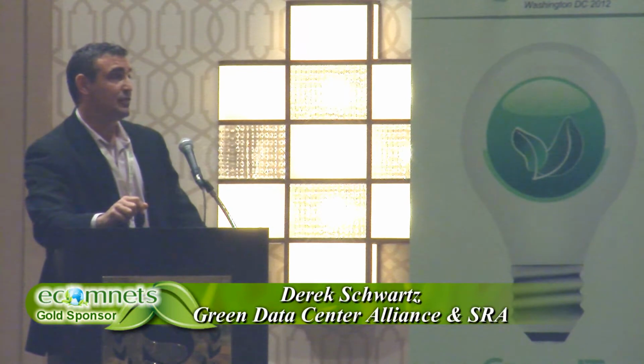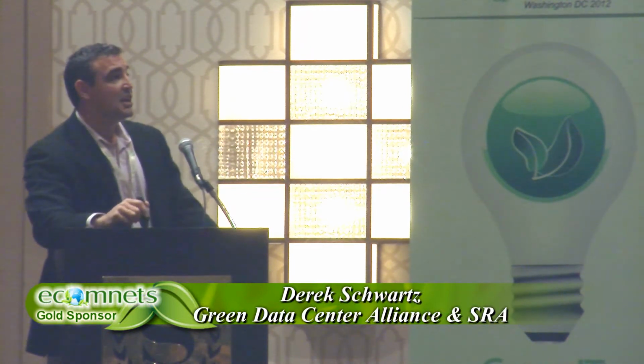This is what we did for one of the pilot programs that we did in New York. So it was 30,000 square feet of data center broken into 8 cells. In a half a day of work with an air speed temperature gauge and a FLIR camera, an infrared camera, we did a half a day walkthrough of 4 of the cells, and we're able to say that half a day of the compiled report, so a day of consulting.